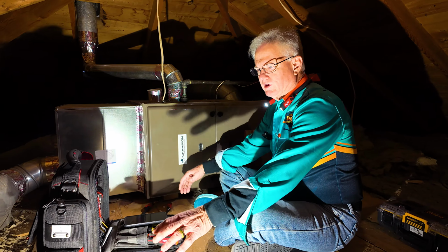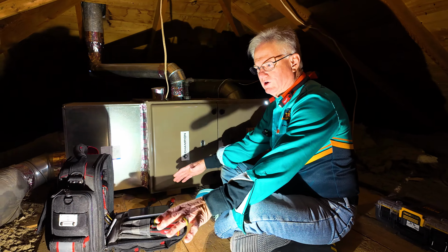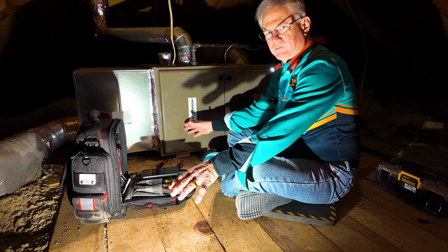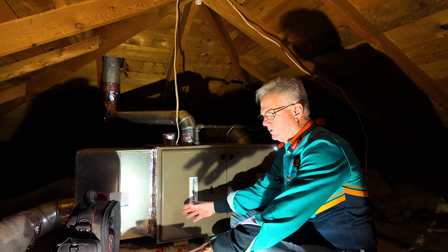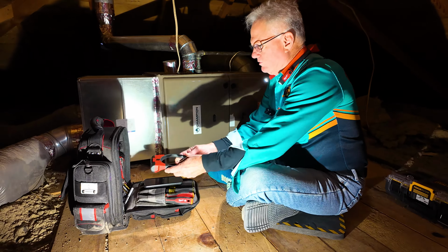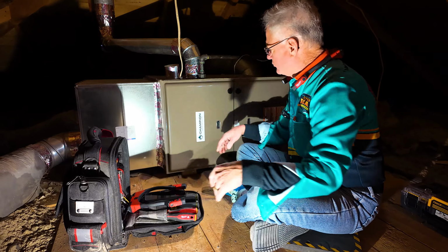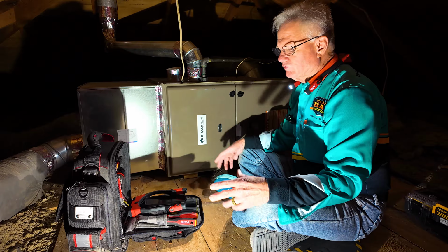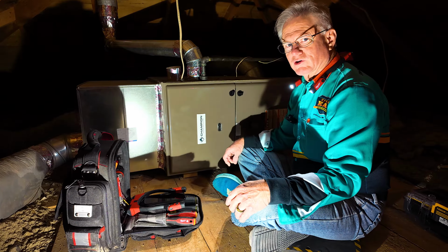So that indicates an intermittent type of situation, and the air handler was working and the gas fired up and it was blowing warm air. So it all seemed to be operating properly. Usually, when you have an intermittent type situation, it's usually a maintenance issue, which is often related to the flame sensor almost certainly being dirty.